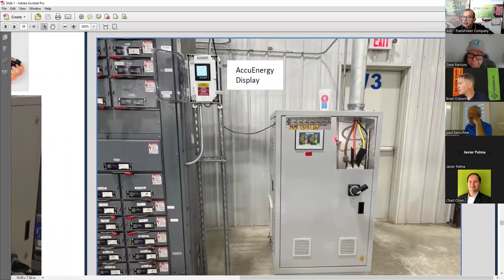Javier and Chad, this is very important. You see this? This is supplied by the factory now, because in 2009 or 2010, we had an arc flash because the installers had these 45-degree lugs that they did not install. They installed straight lugs coming from the breaker and terminated the wire, and the wires were too close. So it created an arc flash. So the voltage jumped from one to another.